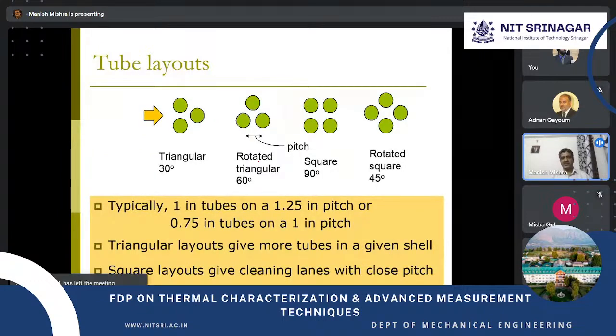Now comes tube layout. What happens when it's a multiple tube variety like a shell and tube heat exchanger where the number of tubes is too large? We can pack the tubes in many fashions, like triangular or rectangular. These are the most commonly used varieties — rectangular, also called square pattern, and triangular pattern. Within triangular, it may be rotated or non-rotated.